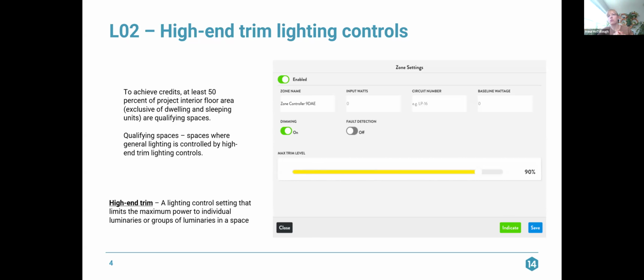So high-end trim lighting controls, for those of you who aren't aware what this is, it's a lighting control setting that limits the maximum power to individual luminaires or groups of luminaires in a space. So what that means is that, for example, I have this picture of these controls, and it has a zone name. So we have a zone controller. The maximum trim level is 90%. So no matter how high they put the dimmer in the space, those light fixtures are only going to put out a total of 90% of their maximum wattage.